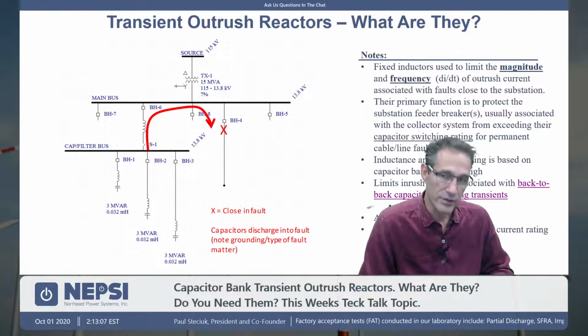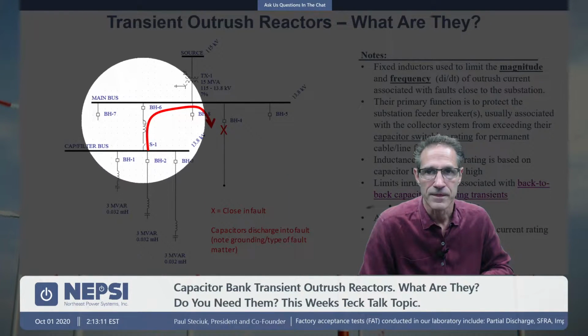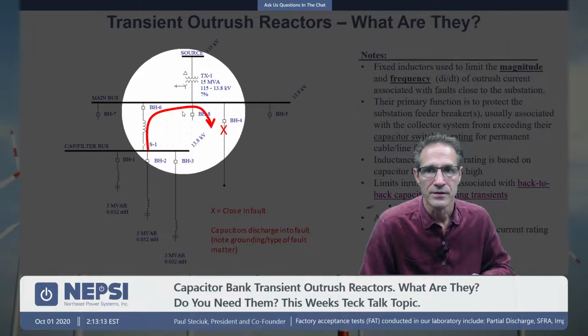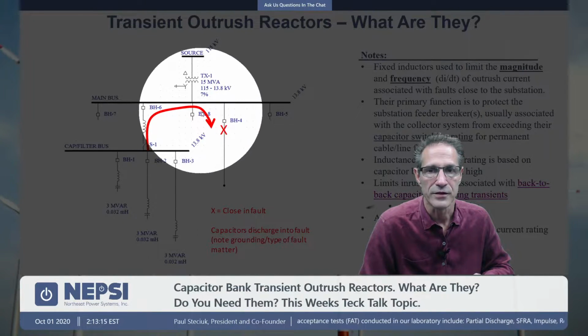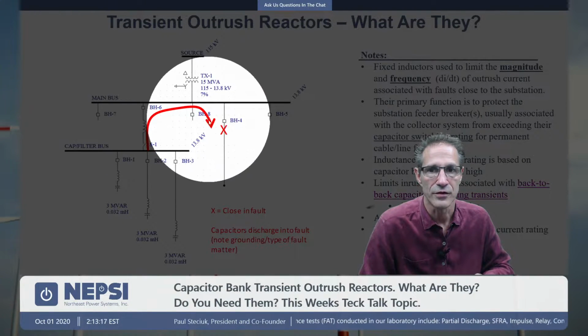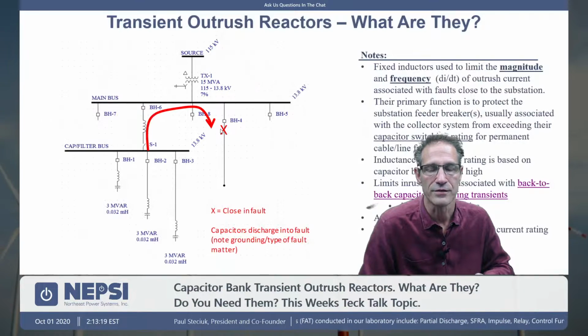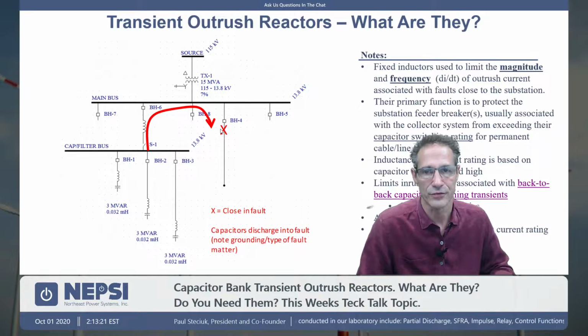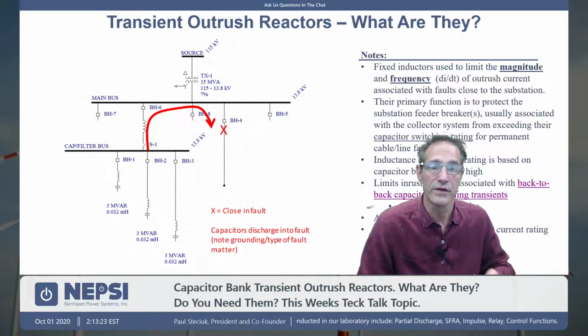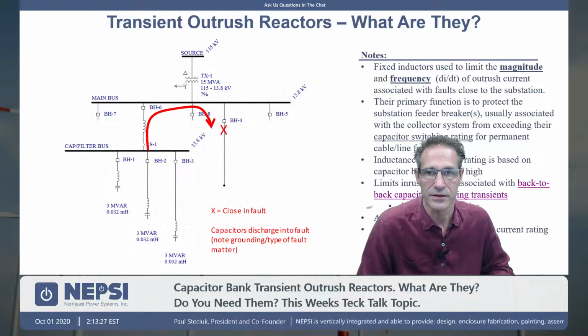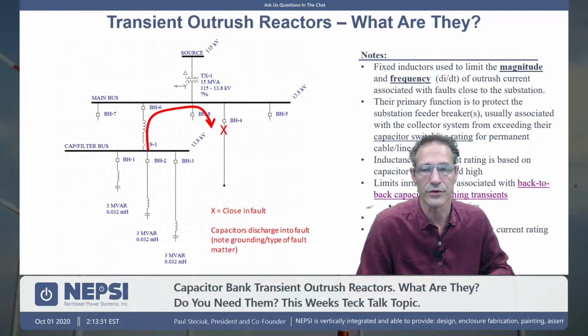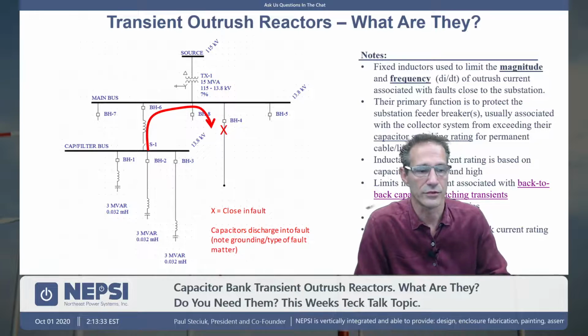And so the objective of putting in an outrush reactor is to add enough impedance to bring down the di/dt and the peak transient current that you would see at this location for a fault condition. That's really what we're looking for. So we have developed a calculator. We're going to go through that in a moment, that you can use to do this analysis to determine whether or not you need an outrush reactor.